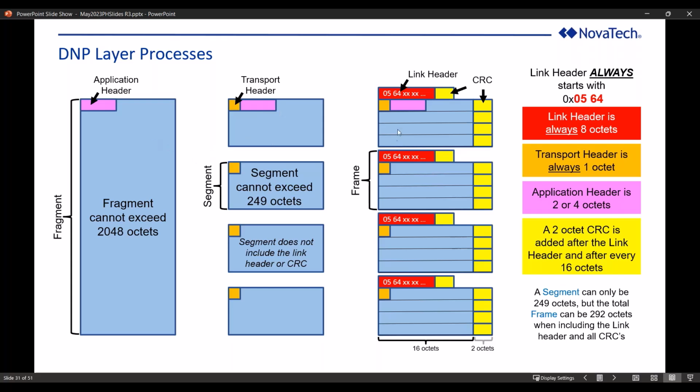And then your data link layer, which is now putting it in an envelope, quote unquote, with our real world analogy, is prepping it to be sent. This is where you put in your addressing. Anyone who's seen a DNP3 data packet knows it always starts with hexadecimal 0564. We don't know why. Whoever invented DNP3 just used those 2 bytes to indicate the beginning of the data packet.